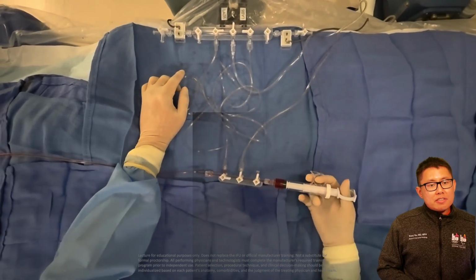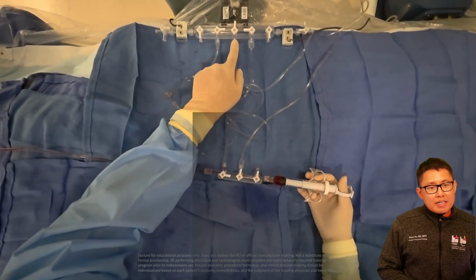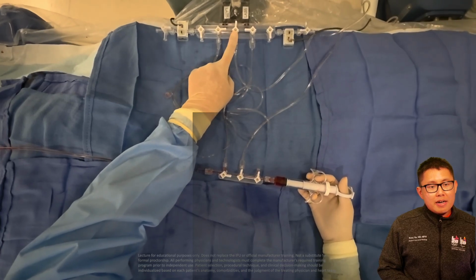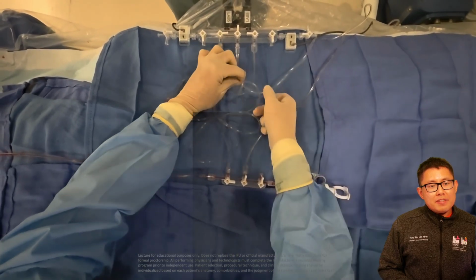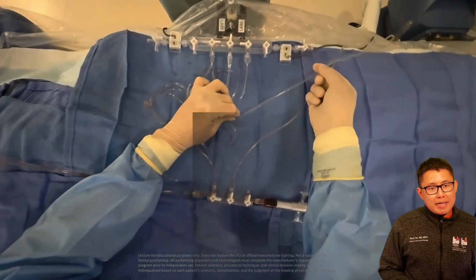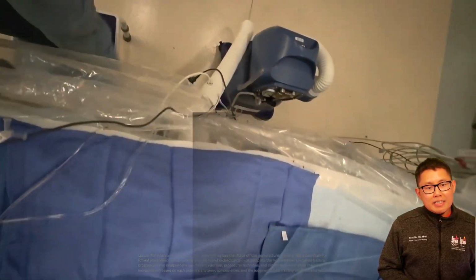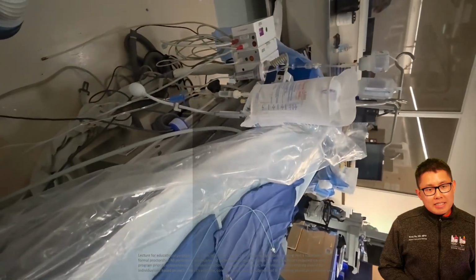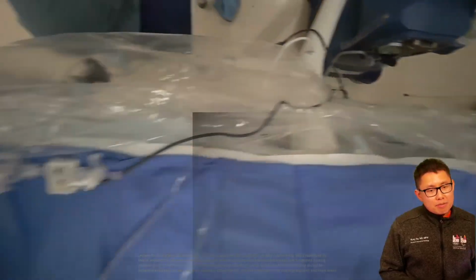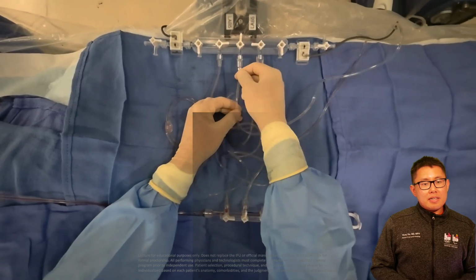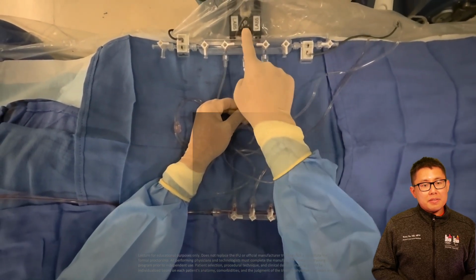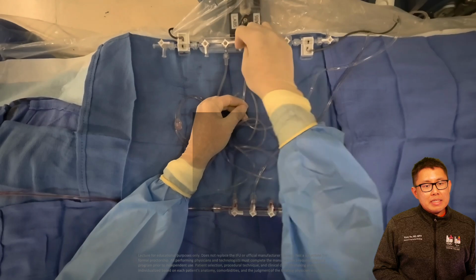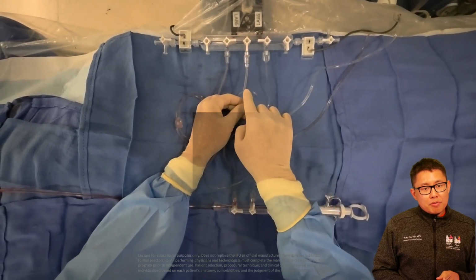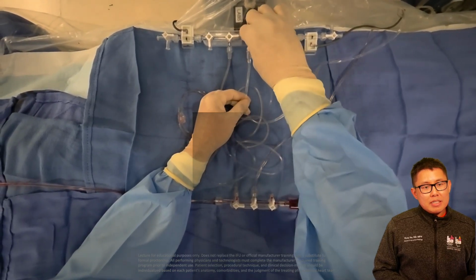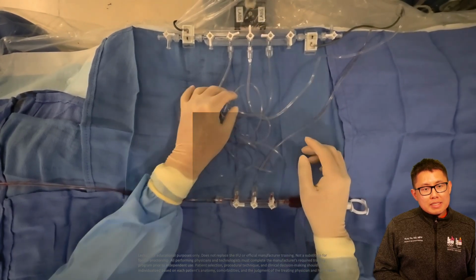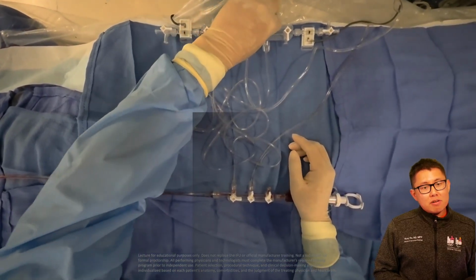We have V2, V3, and V4. V2 and V4 are connected to either the 3-port manifold or directly to a catheter. And V3 is connected to the saline pressure bag. So let's follow this V3 line to see for ourselves with our own eyes that that is a saline pressure bag and that the pressure is up. That allows the saline to drip forward when you have that valve open. So now you see the long arm is pointing down. We have closed the saline port. If the long arm is pointing up, then we have opened the saline port. It can flow either leftward to V2 or rightward to V4.